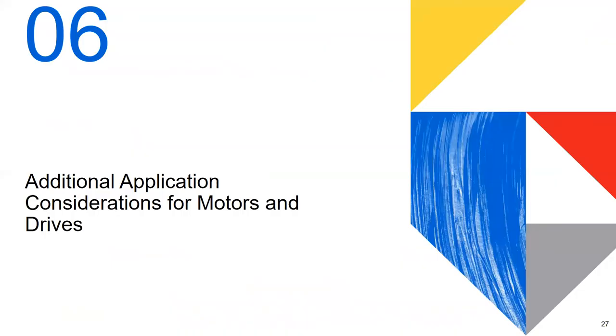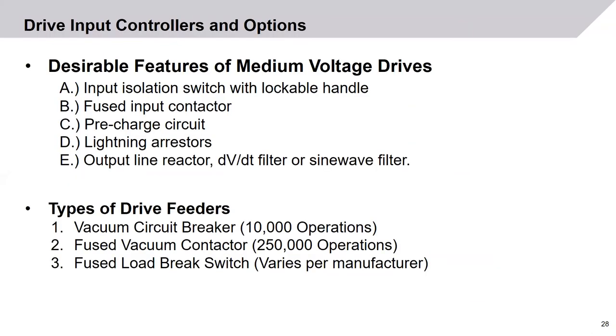Additional application considerations for motors and drives. Desirable features for medium voltage drives include: input isolation switch with lockable handle, fused input contactor, pre-charge circuit, soft charging of not only the transformer but also the DC bus, lightning arrestors, output line reactors, and dV/dt filters or sine wave filters to extend motor lead length. Different types of drive feeders include vacuum circuit breaker — normally good for 10,000 operations before maintenance; fused vacuum contactor — 250,000 operations before maintenance; and fused load break switch — operations vary per manufacturer.